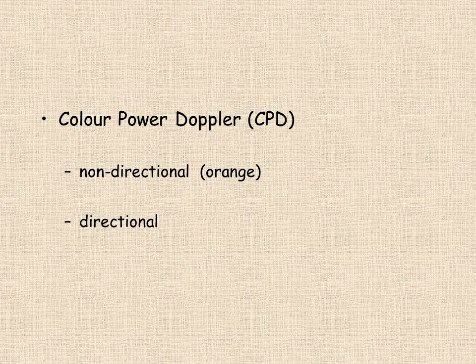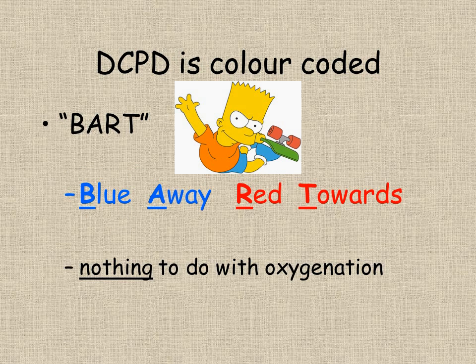This color power Doppler system can be non-directional, in which case all flow is depicted as orange or directional. Directional color power Doppler is color coded such that blood flow away from the probe is colored blue, and blood flow towards the probe is colored red. This allows you to differentiate between arteries and veins by adjusting the probe position, and has nothing to do with oxygenation.